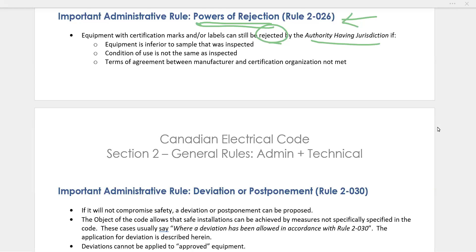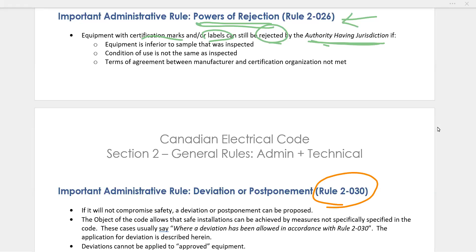Equipment can also be rejected if it's being used in a condition not associated with its certification — for example, the inspection labels were for a certain use but it's being used for a different use. It can also be rejected if the terms of agreement between the manufacturer and the certification agency haven't been met. So regulators and the Authority Having Jurisdiction do have the powers to reject equipment even when certification marks and labels are present.